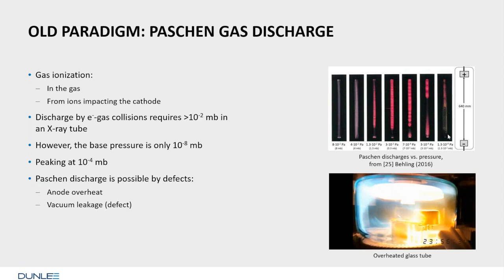So what is an X-ray tube doing? Well, X-ray tubes typically have gas pressures orders of magnitude lower than all these gas discharges. We have in a good X-ray tube a base pressure in the ballpark of 10 to the minus 8 millibar, which is peaking to 10 to the minus 4 if the anode is very, very hot. If the anode is very, very hot, it creates carbon monoxide, and then the tube gas pressure is rising, but it's still far away from these 10 to the minus 2. It's 2 orders of magnitude lower. So the PASCHEN discharge is not the regular cause of arcing.